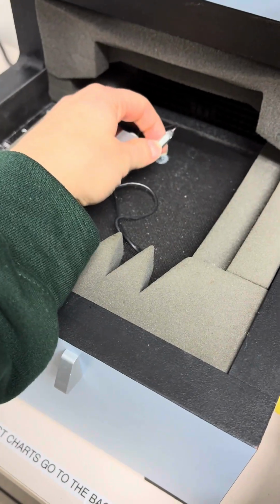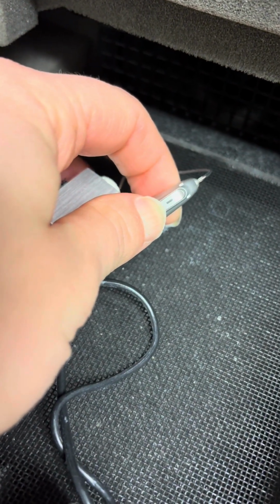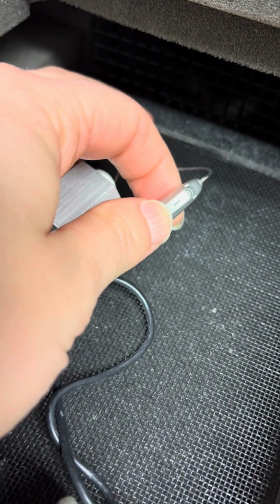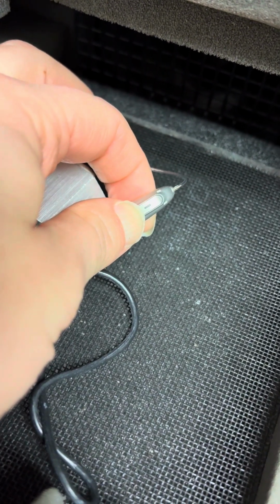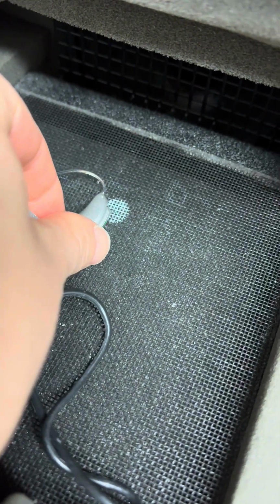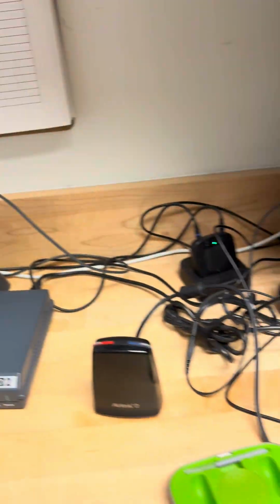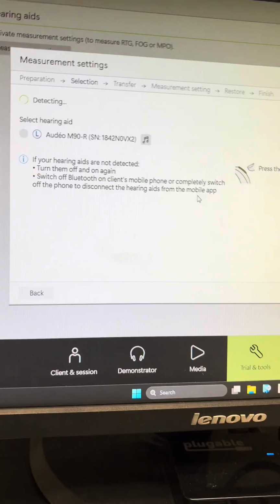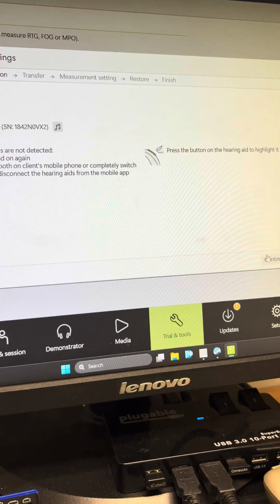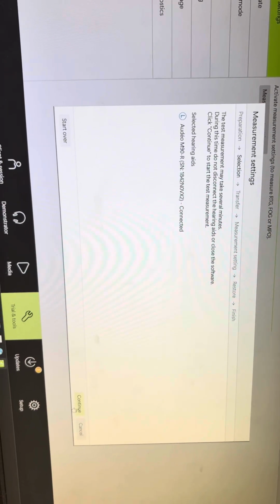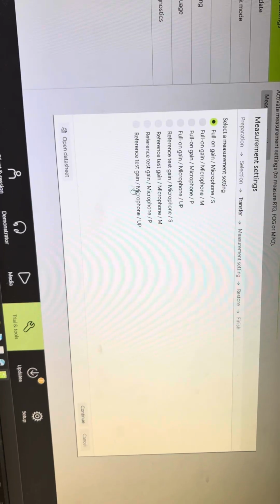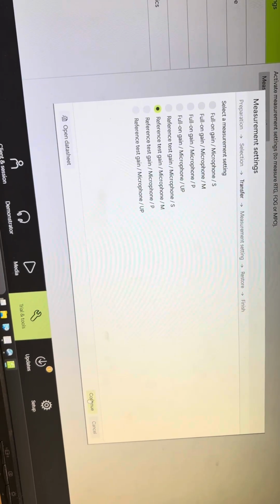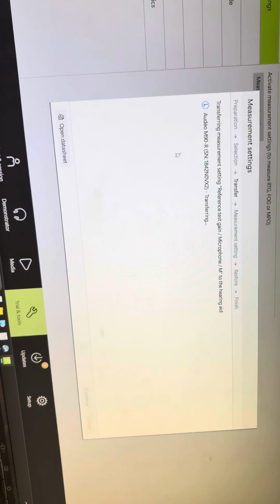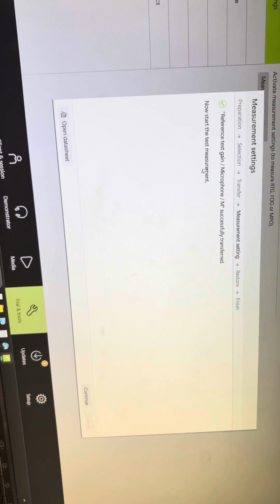So grabbing the hearing aid, holding it down, off, and on. Kind of want to make sure that hearing aid setup is proper again. It detected it, so selecting, continue. And then reference test gain, same receiver. Going to set it in reference test. Now we can start that measurement.